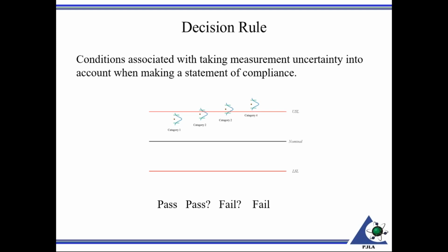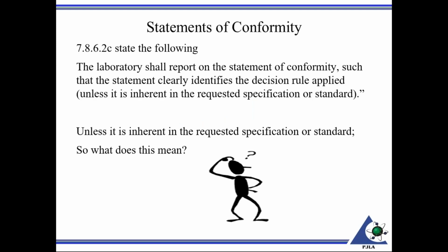You also will need to, as per contract review, section 7.1.3, even prior to reporting uncertainty in the decision rule, gain the customer's agreement as to the decision rule that you're going to use. Still under here, 7.8.6.2 still incorporates the decision rule. The laboratory shall report on the statement of conformity such that the statement clearly identifies the decision rule, unless inherent in the requested specification or standard.